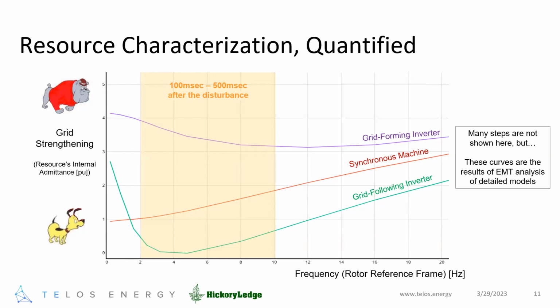At the low frequency side on the left it's high—it has some terminal voltage regulation, but it takes time to work. So it shows up at low frequency, but then tails off and is pretty low in the band I'd consider fairly critical. So grid following inverters do not provide the grid strengthening effort that synchronous machines do, according to this graph and basically all of our understanding.